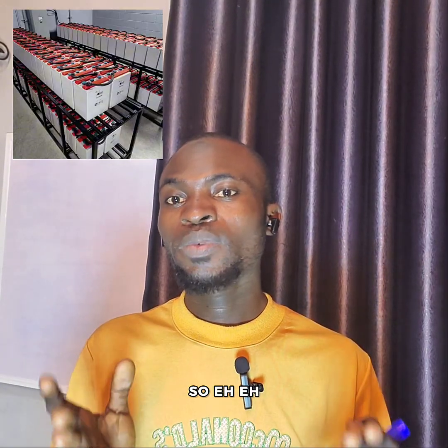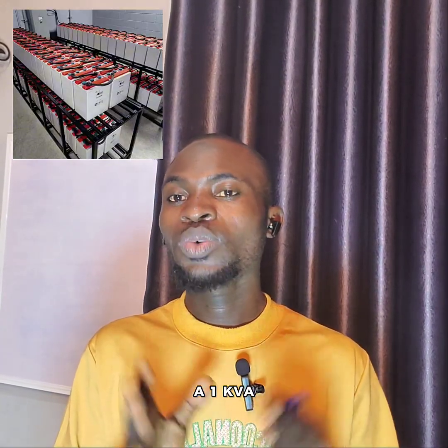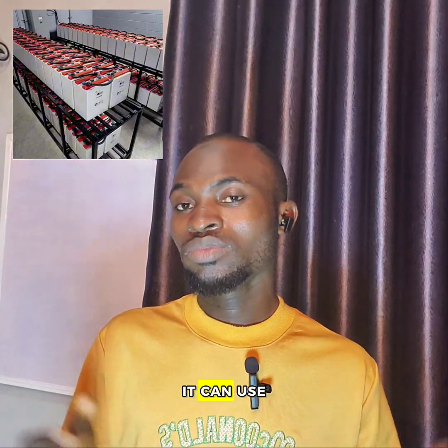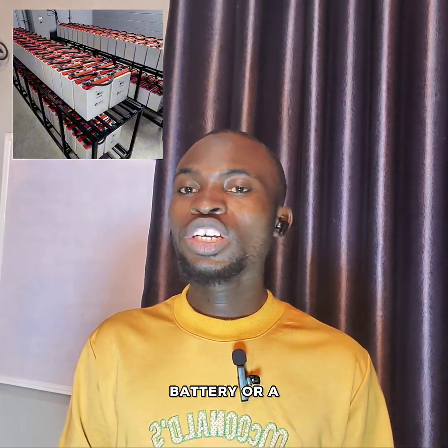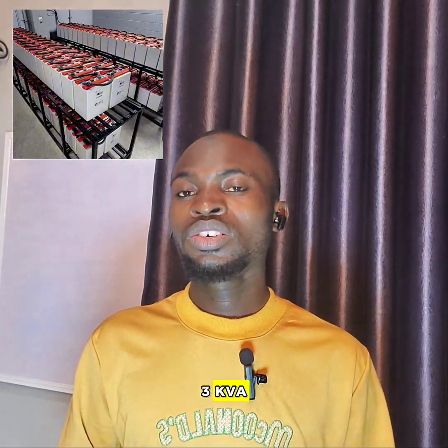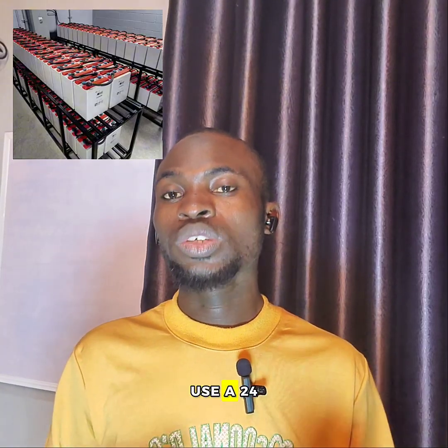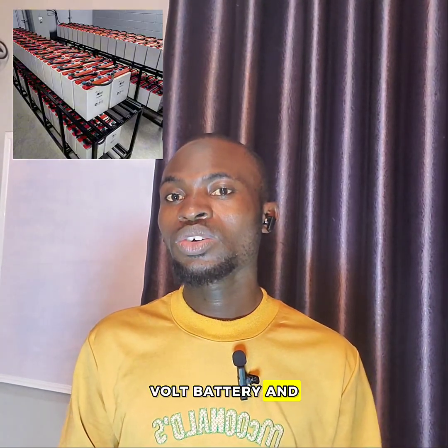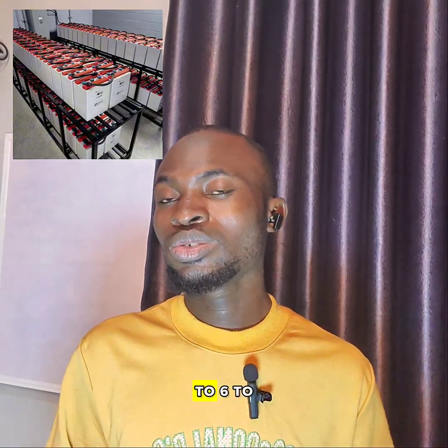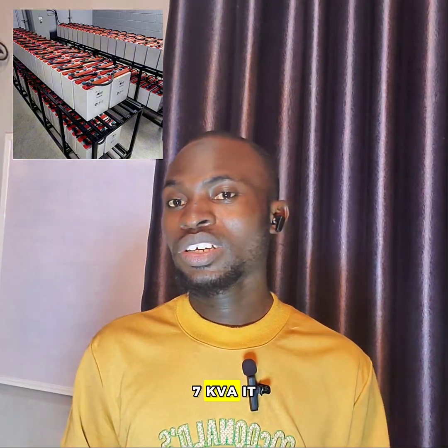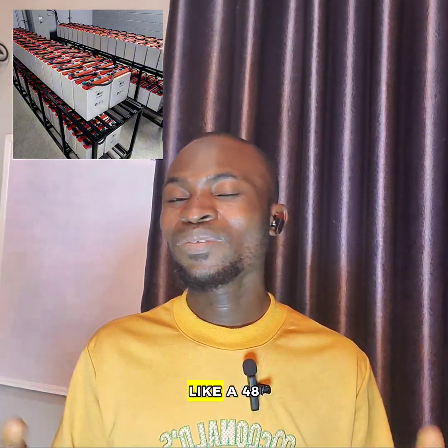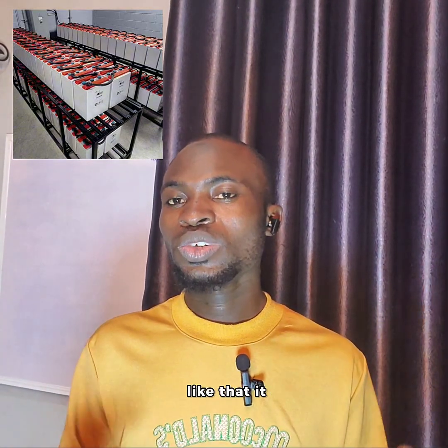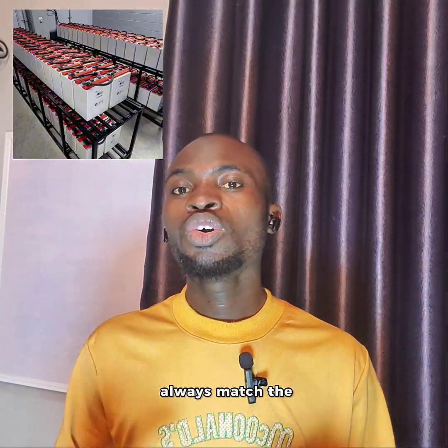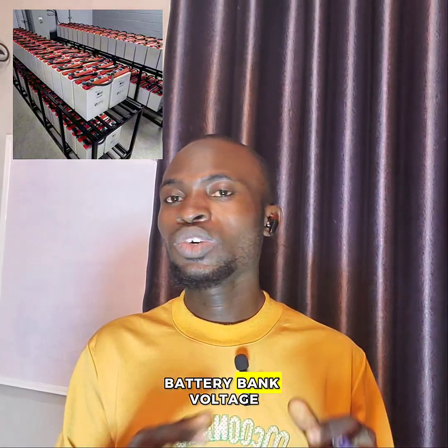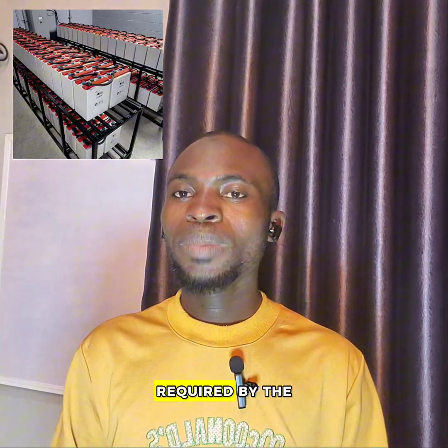So for an inverter size of 1 kVA, it can use a 12 volt battery. For a 2 or 3 kVA, you can use a 24 volt battery. And for like 6 to 7 kVA, it will use a 48 volt battery. So it has a range like that. Always make sure you match the battery bank voltage required by the inverter.